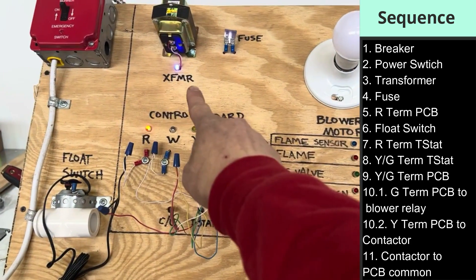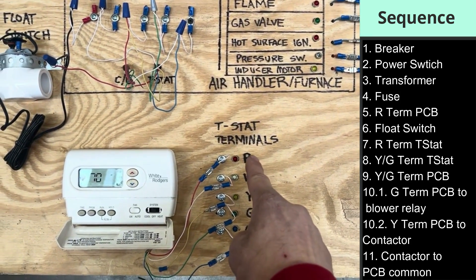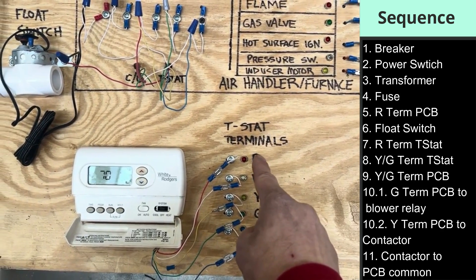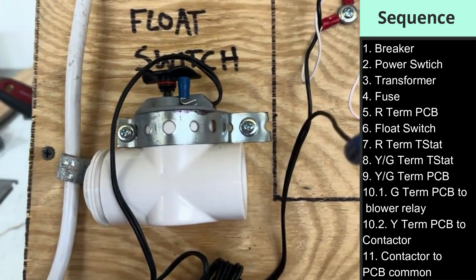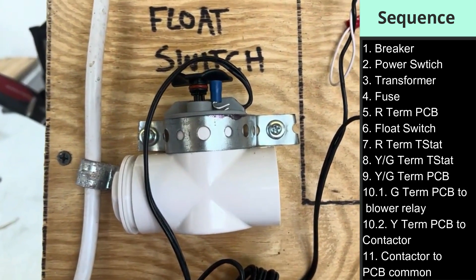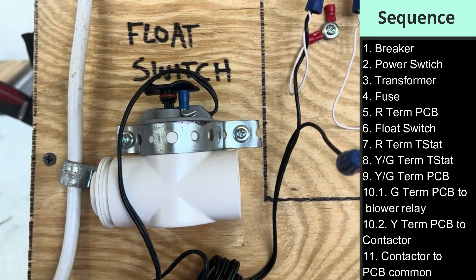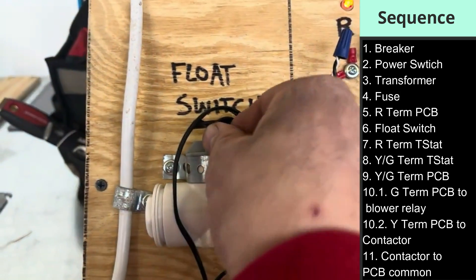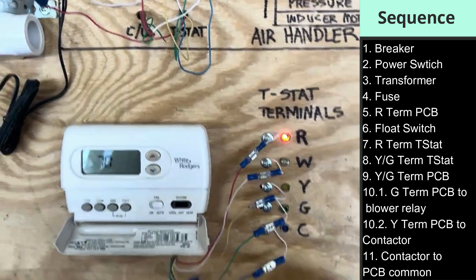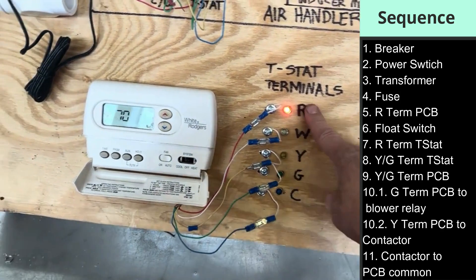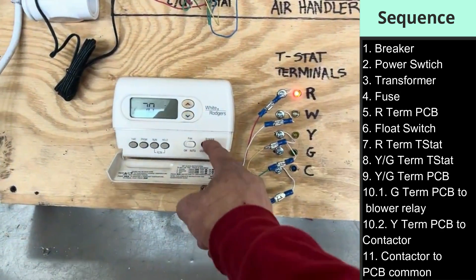For example, if I walk up, put the thermostat in cooling mode, and absolutely nothing is happening, I might check if I have power on that R terminal. If I don't, the problem is somewhere in the sequence prior to that point. Here's an example: I have power off my transformer, power going through my fuse, power going to my R terminal on the control board, but no power on the R terminal at the thermostat. Looking at the sequence, what's in between? It's the float switch. I rigged it to lift the float switch — this means we have a drainage problem, a clogged drain line or a filled drain pan. Clean that line out, the float switch goes back down, and power is restored.